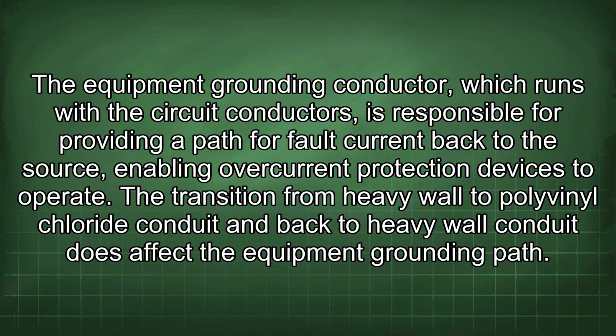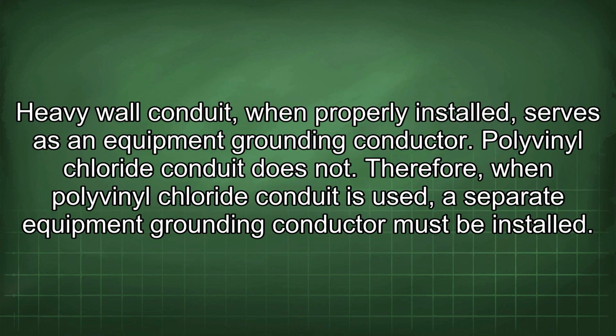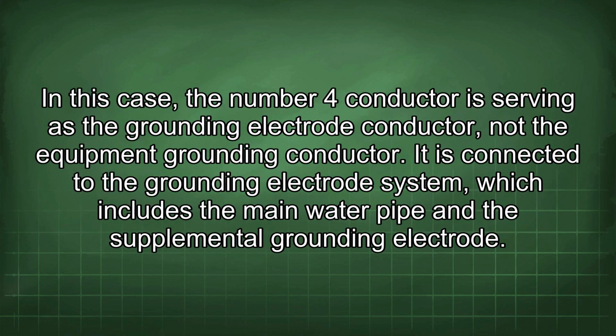The transition from heavy wall to polyvinyl chloride conduit and back to heavy wall conduit does affect the equipment grounding path. Heavy wall conduit, when properly installed, serves as an equipment grounding conductor. Polyvinyl chloride conduit does not. Therefore, when polyvinyl chloride conduit is used, a separate equipment grounding conductor must be installed. In this case, the number 4 conductor is serving as the grounding electrode conductor, not the equipment grounding conductor. It is connected to the grounding electrode system, which includes the main water pipe and the supplemental grounding electrode.